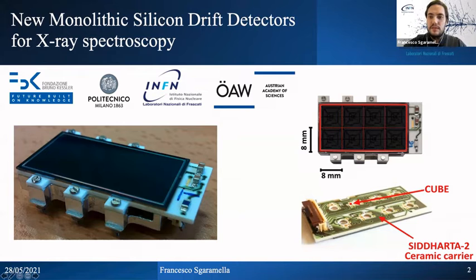Each array consists of 8 SDD units organized in a matrix with a 1 millimeter dead region along its border. The silicon wafer is glued on a ceramic carrier, which provides the polarization to the single units and houses a dedicated preamplifier, the CUBE. Each CUBE is bonded to the corresponding SDD anode, and the device is screwed on a high purity aluminum support, which provides the cooling power.